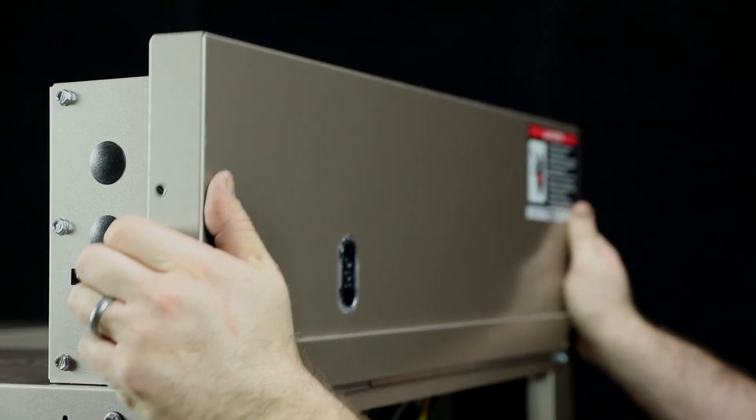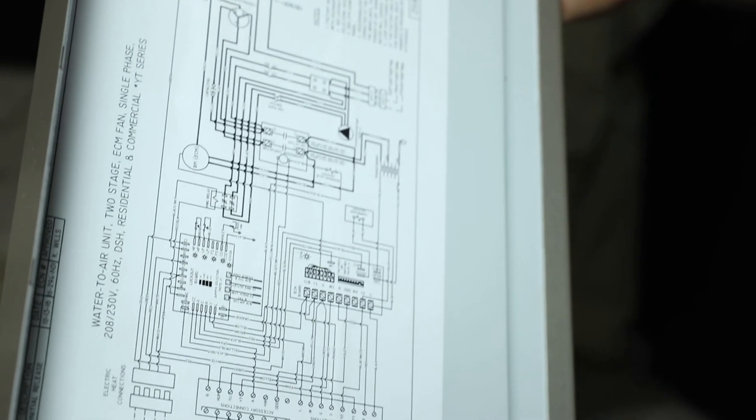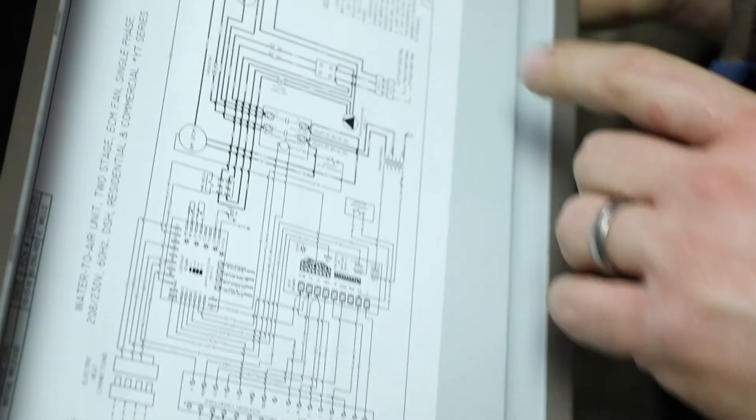We recommend using zip ties and attaching any excess wire to tubing insulation. Secure wires so they do not come in contact with any copper tubing. Complete the wiring connection in the control box using the wiring diagram inside the control box cover as needed. Pumps must never run dry. Do not power pumps until flushing and purging is completed.